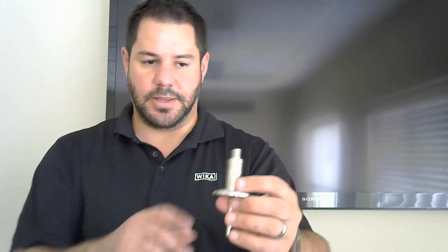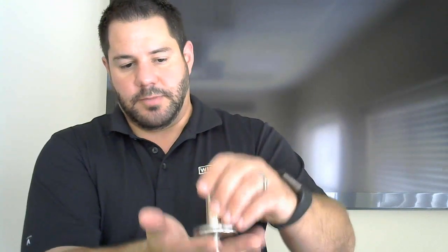This design is great if you don't have to have the logic—you don't need HART, fieldbus, any of that. You just want a 4 to 20 signal going back to a DCS system. It can be tri-clamped into the side of a tank, or into a T, whatever. You've got your 4 to 20. Then if you have to calibrate it, you have to un-tri-clamp it and calibrate it.